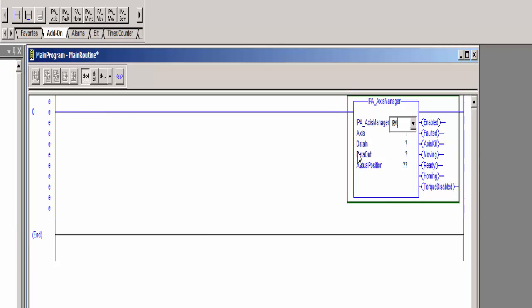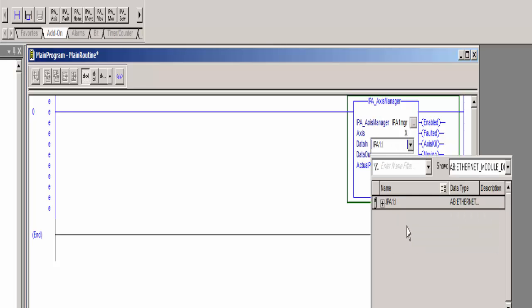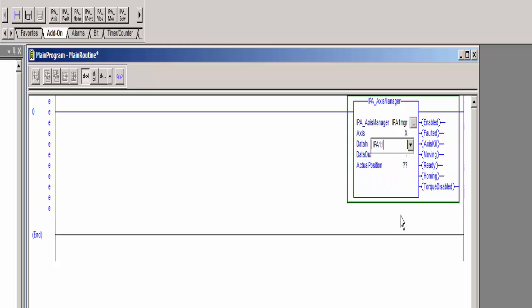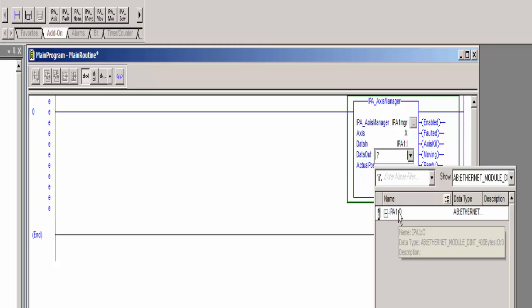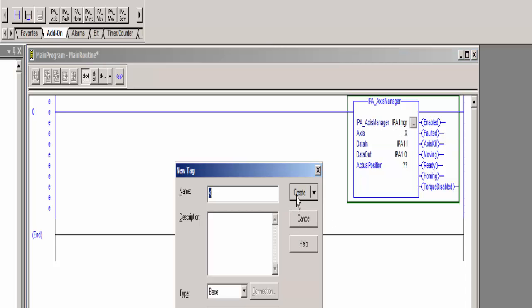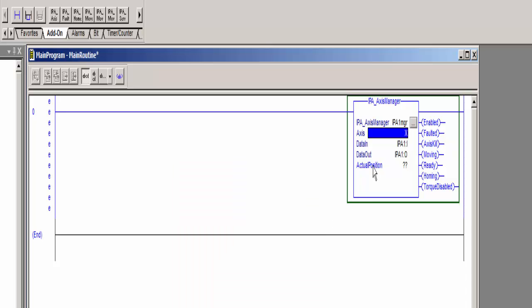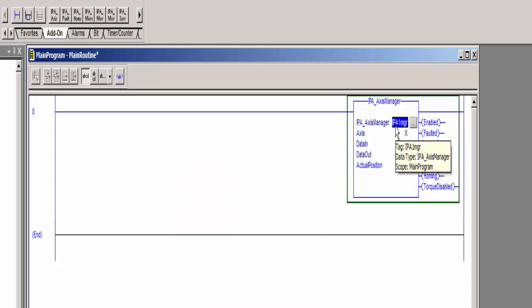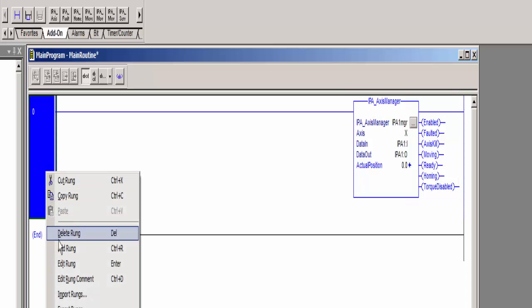So I'm going to name this IPA1mgr, which is the name of the function block or the add-on instruction. And then I'm just going to name it X. And for the data in and the data out, those have already been defined, but you need to go ahead and select those in. And then select the outputs. And the error indication means that you need to do a control W to create that tag, and the same thing with the function block itself. Once you do that, the E's disappeared, you have no errors, and then you'll want to actually do something.